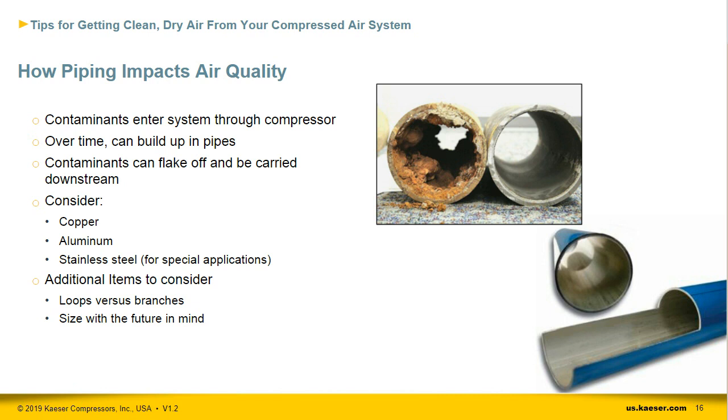If you need clean, dry air, I can suggest copper or aluminum. Stainless steel is also an excellent choice, but it's much more expensive. It's typically only required for special applications.